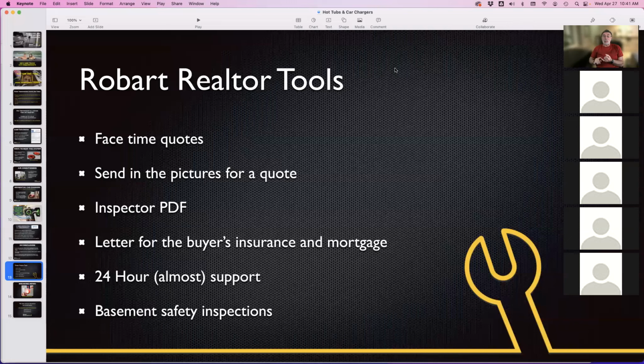What you're going to find out is: is it a 60 amp service, older than 1965? Is it aluminum wiring, 1965 to 1968? Is it knob and tube wiring - something insurance companies are not giving insurance for - that's from the 30s, 20s, and 40s? Other things like basements that were done without permits, that's the last item on the list. But that's something you'll find out if Robart Electric comes in and does these inspections for you.